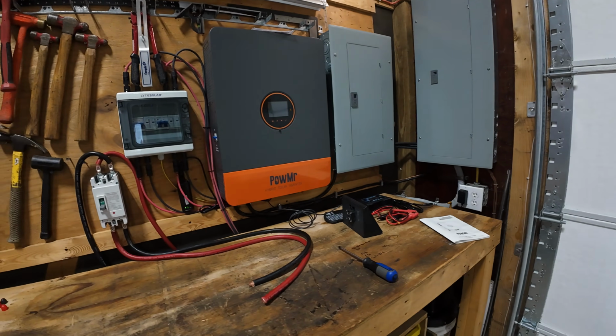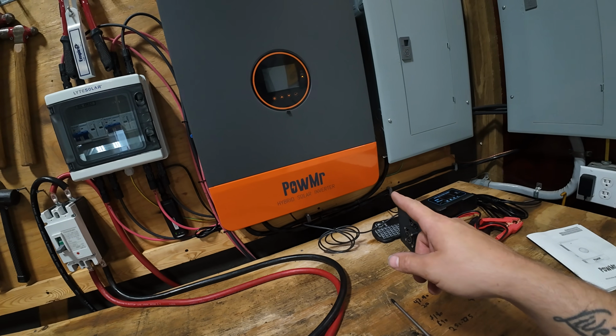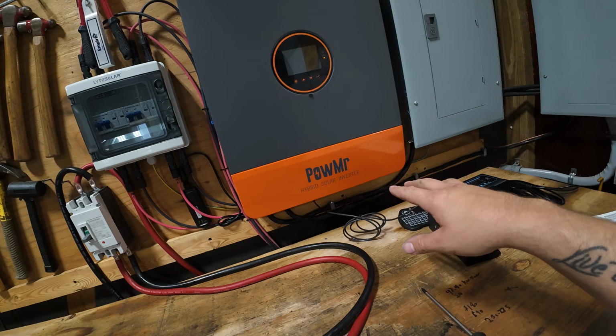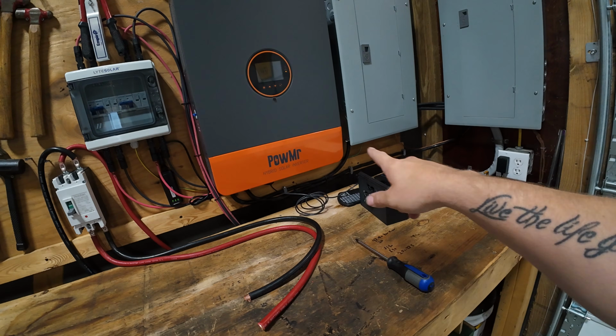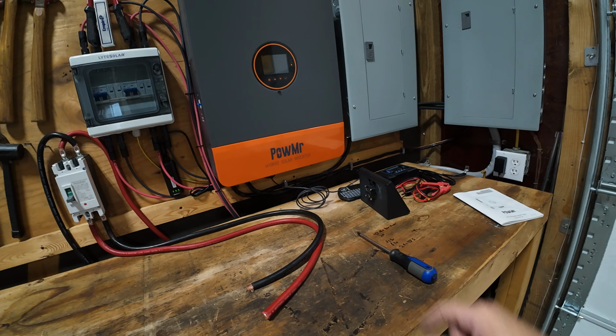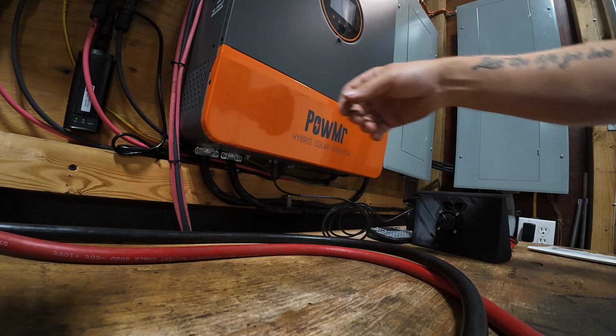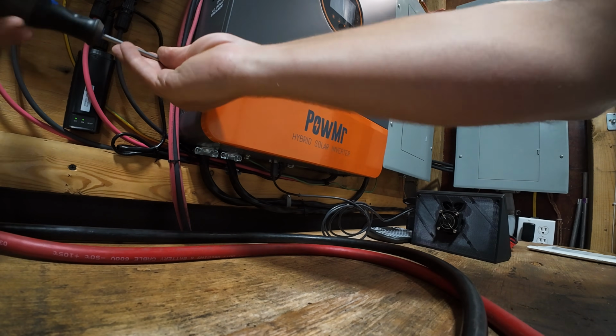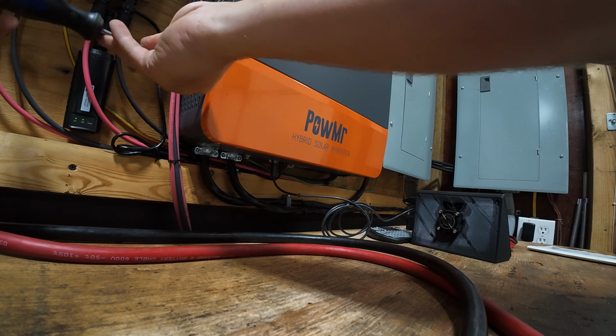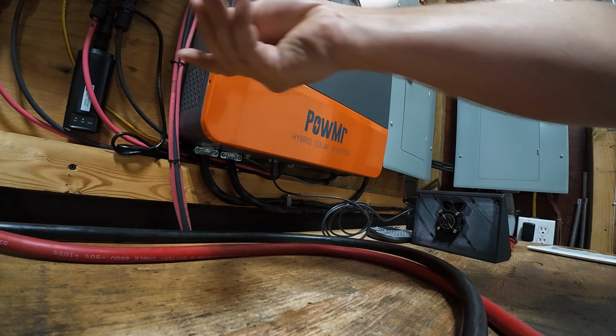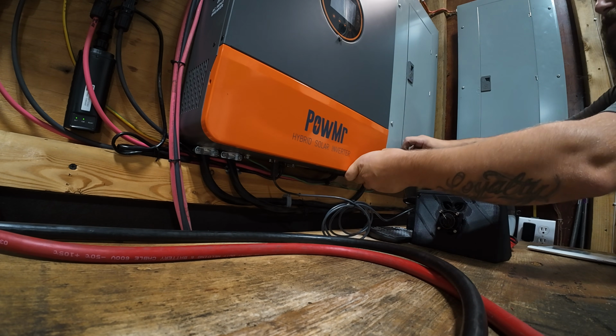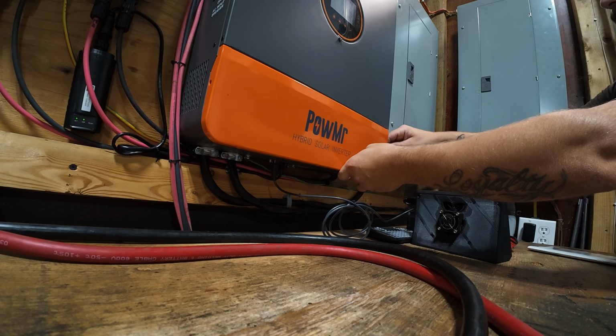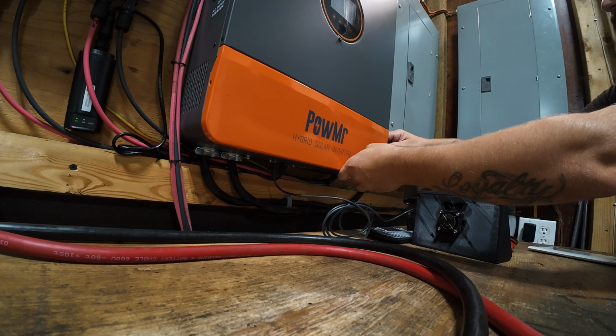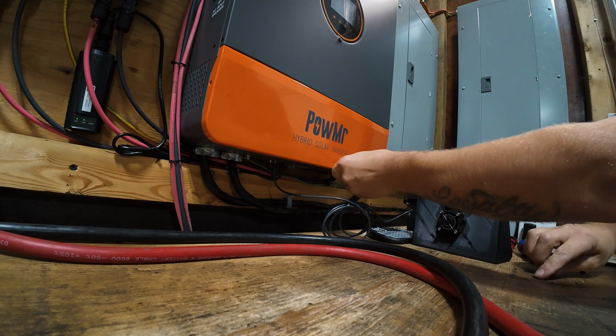So we're going to go ahead and do that, but before we do, I just want to pop this cover off real quick to show you guys the internals, because once I turn the power off, you might not have the greatest view inside here since it'll get pretty dark. To remove this panel, there's just a screw on each side holding the panel cover in place. I don't recommend you ever do this with the power still on - it's very dangerous, so always make sure all the power is off to the inverter before opening this cover panel.